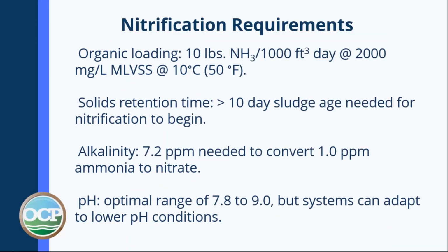Nitrification requirements: the organic loading is 10 pounds of ammonia per 1,000 cubic feet per day at 2,000 milligrams per liter mLVSS at 10 degrees C, that's 50 degrees F. Your solids retention time or sludge age: sludge must be greater than 10 days old for the nitrification process to begin. So it takes older sludge.